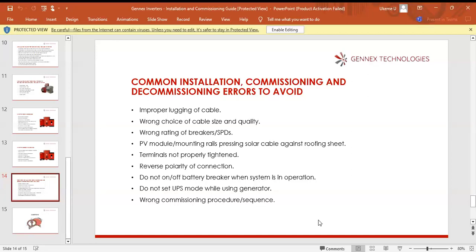Wrong rating of breakers too will just cause a kind of nuisance. If it's lower than necessary, it will just be tripping off. If it's higher than necessary, it won't even trip. It will allow the heavy current to go into the inverter and damage the system. So it's good to choose carefully. According to calculation, there are calculations for all this.